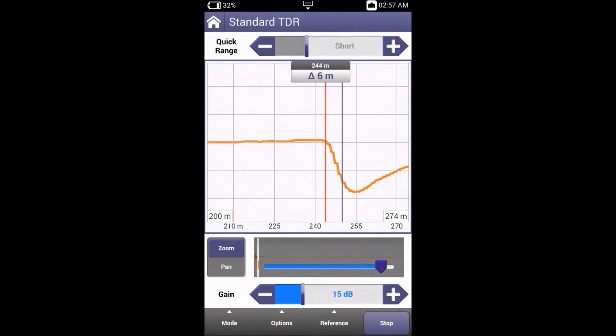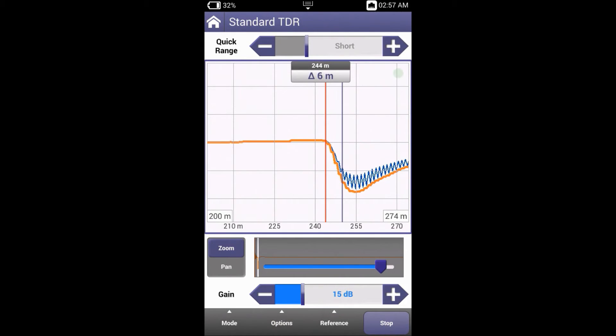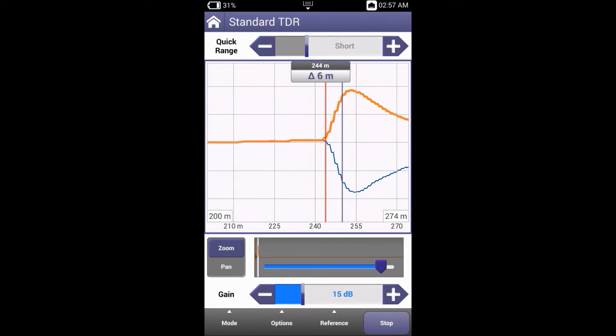Let's demonstrate this through the short that we see on the screen. Now I've got peak hold on. I'll now create an open. And you can see that it's held the difference between the two traces.